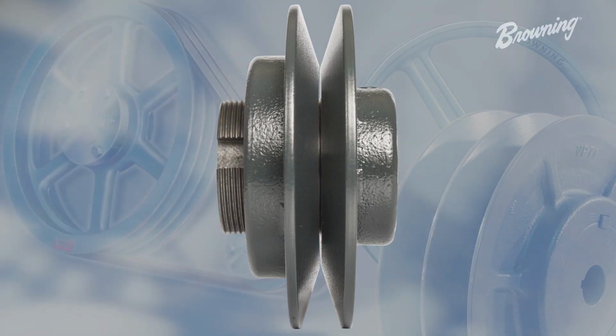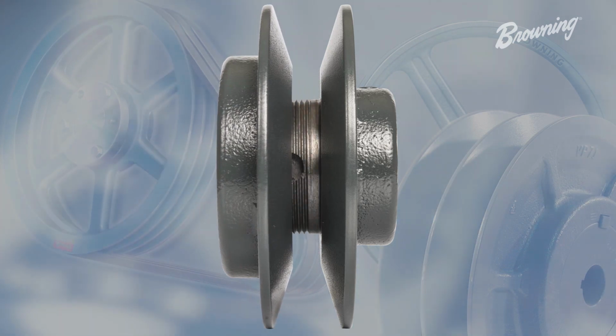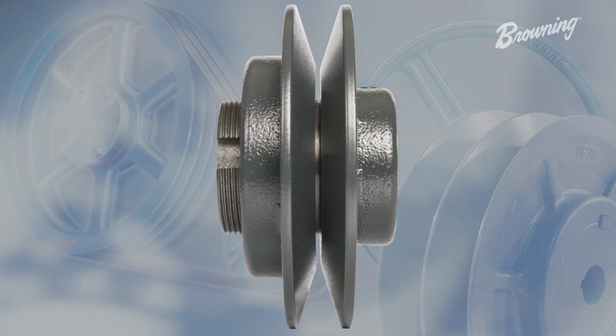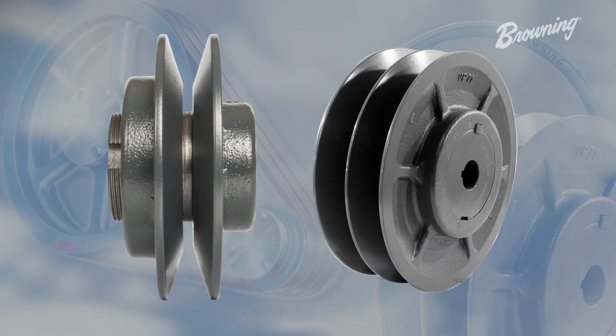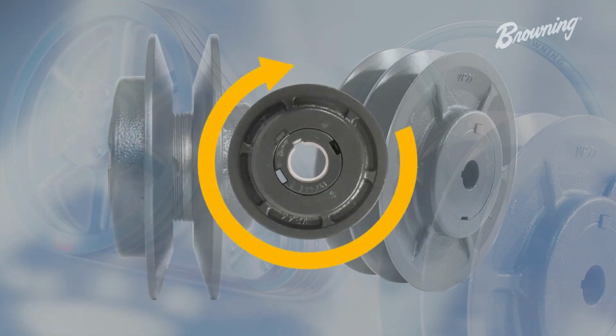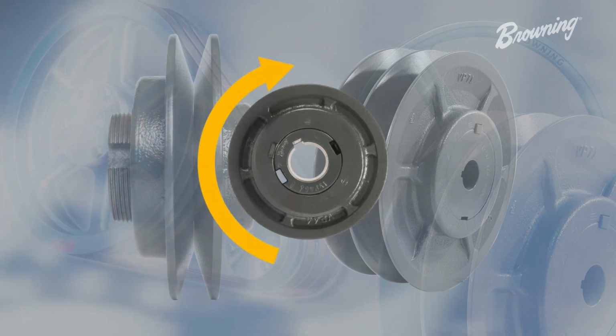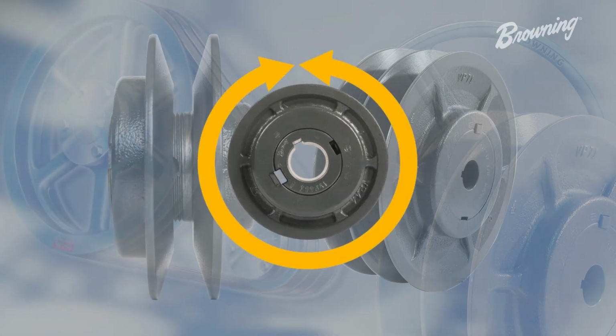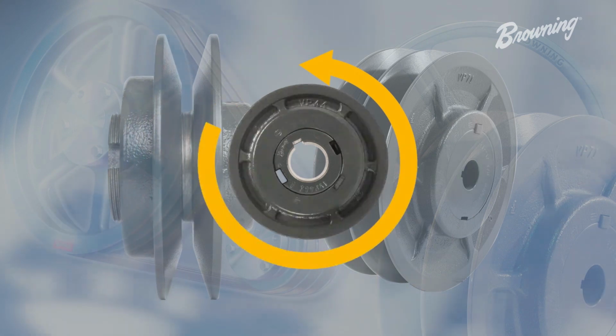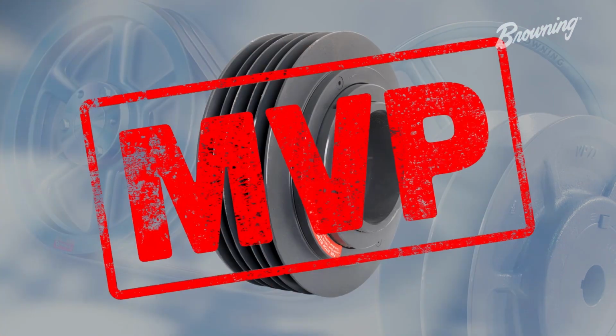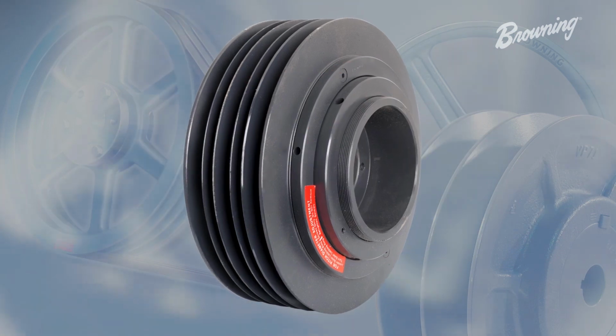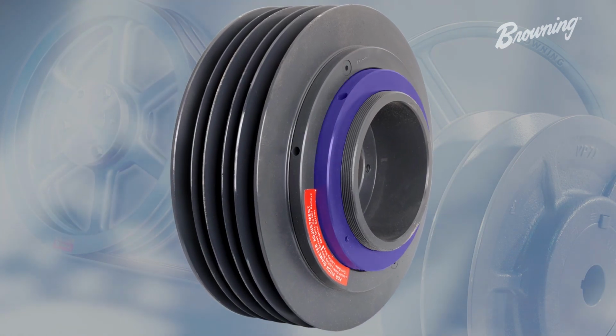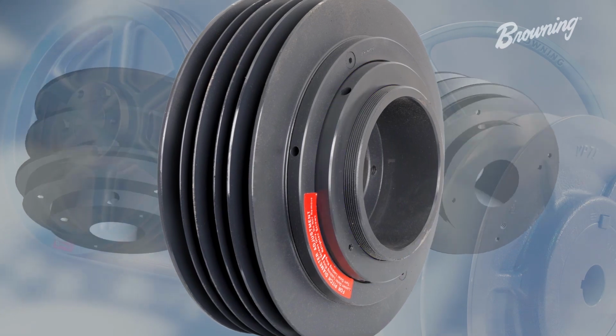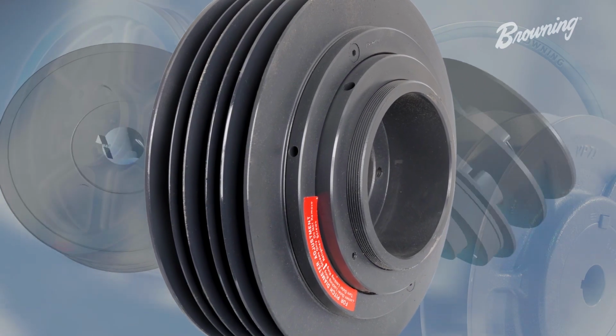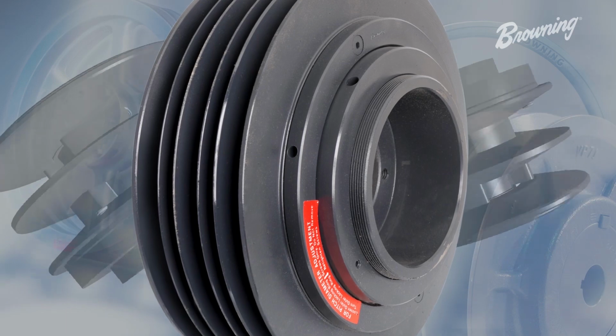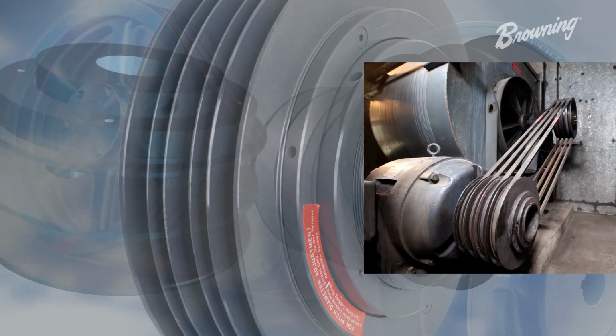There are two types of variable pitch sheaves. First, standard variable pitch sheaves, or VP sheaves, have one or two grooves and a flange on one or both sides that can be rotated in or out to adjust pitch diameter. The second type is what is known as a multiple variable pitch sheave, or MVP for short. These sheaves are 2 to 5 groove and have one infinitely adjustable hub that when turned, adjusts each groove equally at the same time. MVPs are typically used on higher horsepower applications.